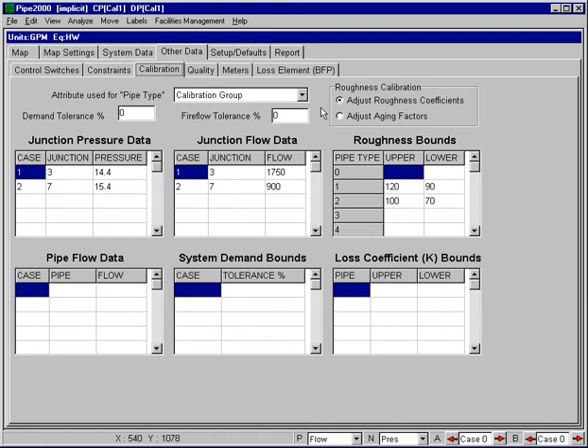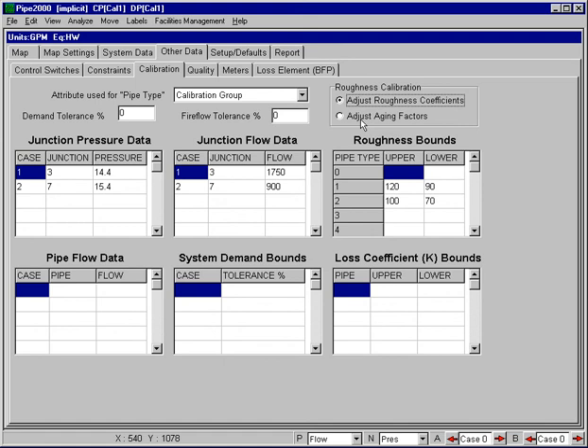If you do that, and then select the aging adjustment factors option here, what the program will then do is to calibrate C factors to match these observed conditions. And then the program will then use the previous C factors 10 years ago and the new C factors here to come up with internal coefficients that the program can then use to project or predict C factors out in the future. So this option allows you to calibrate your C factors, not only for the current condition, but also build in factors that can be used to predict C factors in the future.